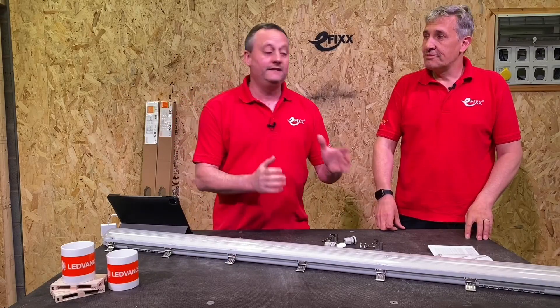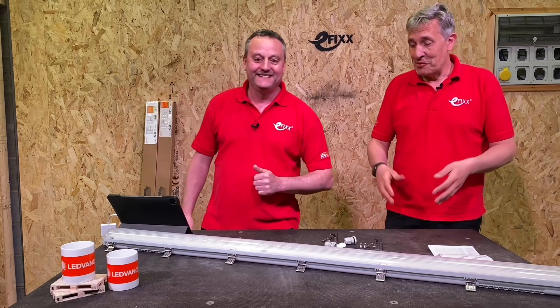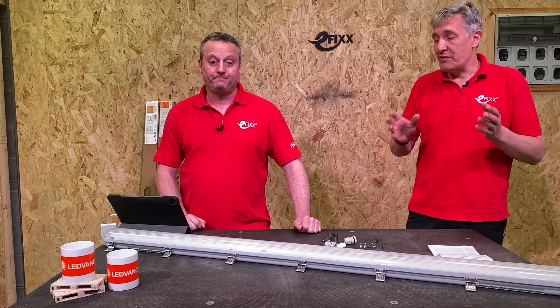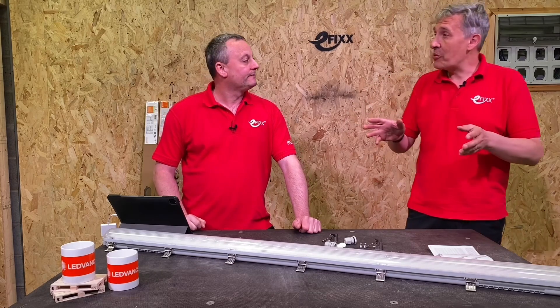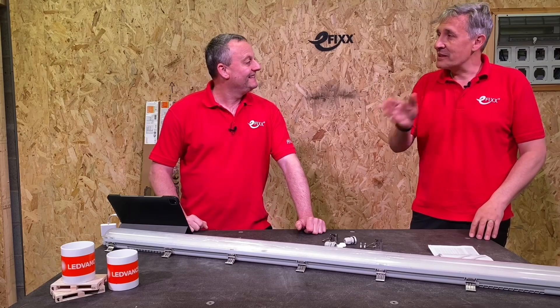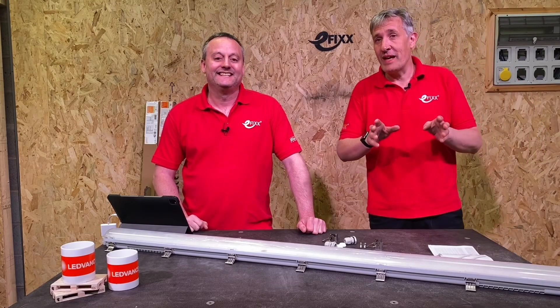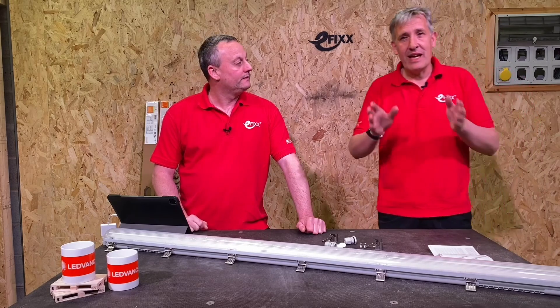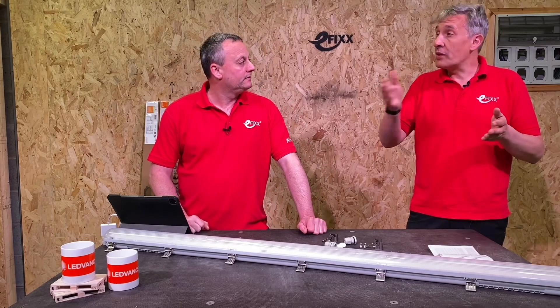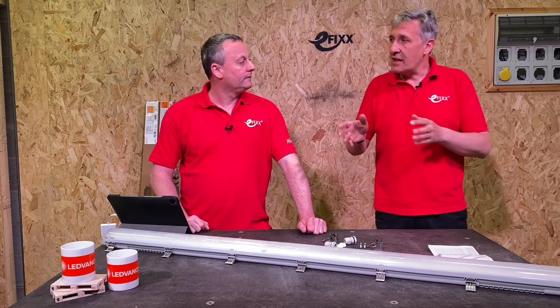You can judge the quality of a light fitting by the amount of data the manufacturer gives you, specifically regarding light output — and the lumen maintenance figures of L70 and L80. Ledvance give you two numbers: an L80 of 50,000 hours — meaning 80% output at 50,000 hours — but they go beyond that, with an L70 at 70,000 hours.